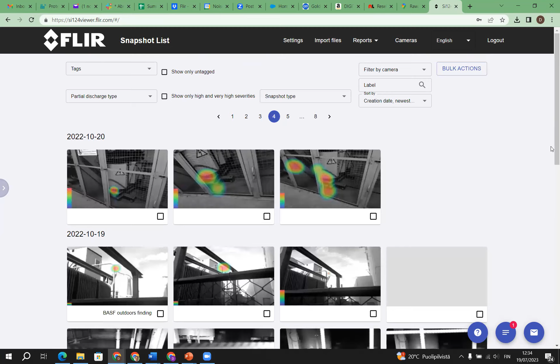This is an example of what we were talking about with cabinet joints. If you cannot open the cabinet, the camera will never give you a partial discharge reading inside, because there's a barrier, the door, and it's impossible for the camera because the sound is intercepted by the door. But in this case, it often happens that if there is a PD, it shows up at the joint of the doors, because the sound is sticking out from there, leaving the inside of the cabinet.